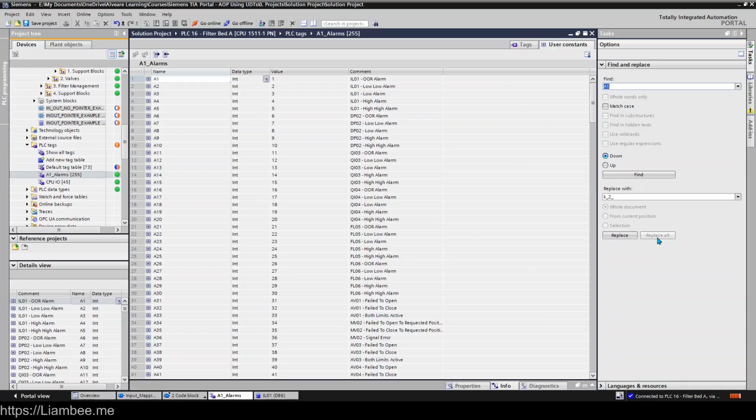And that's it for that, really. So yeah, every single alarm should be tied to a constant, and the constants are used to index the array that we're using to pass information to SCADA or an HMI and to manage the alarm.